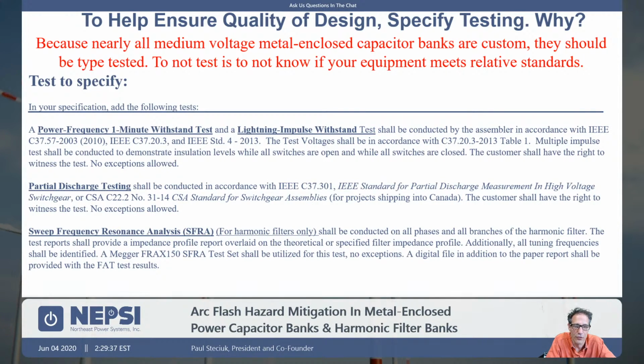If you have a lot of corona, what you basically have is insulation being eaten within the system, and at some point that insulation will degrade. You get tracking, and it will flash over. So being able to design equipment with a minimum amount of partial discharge at the extinction voltage is critical to determining the life of the equipment.